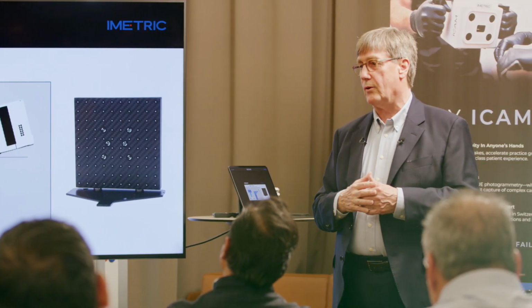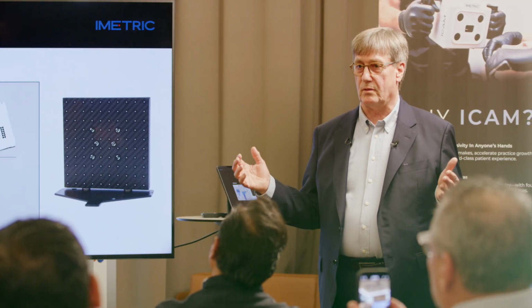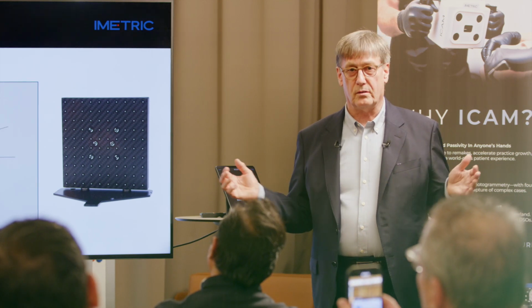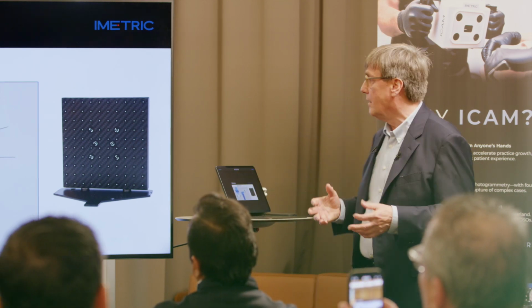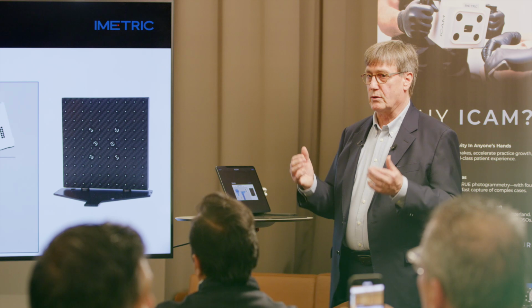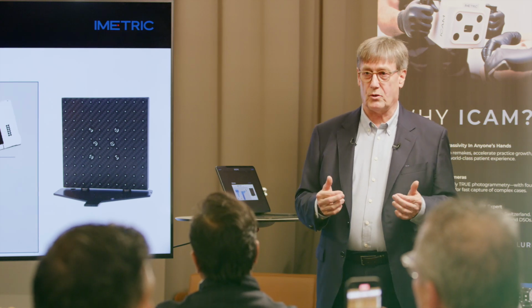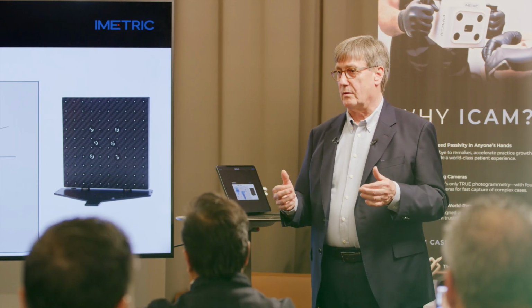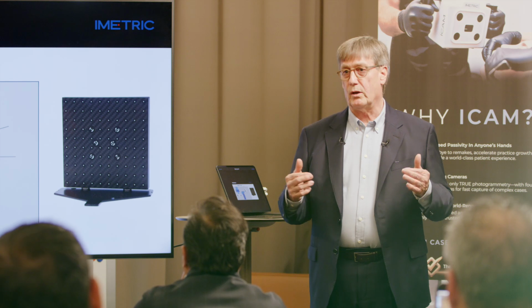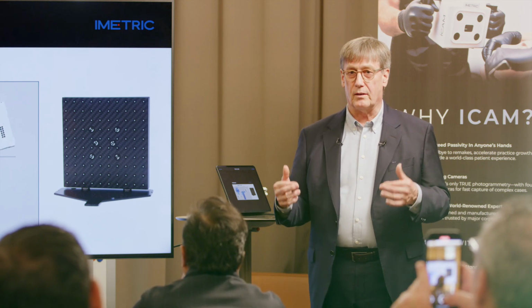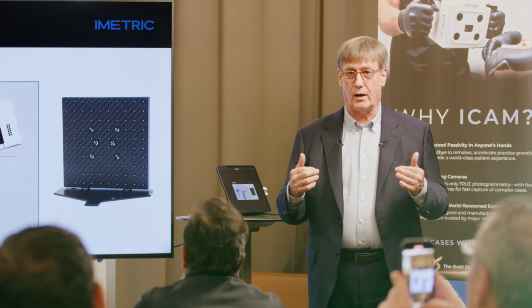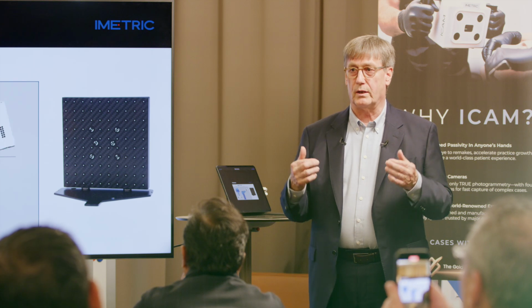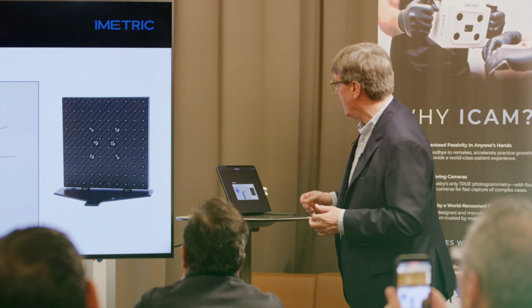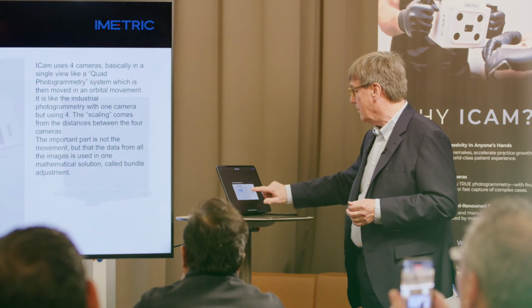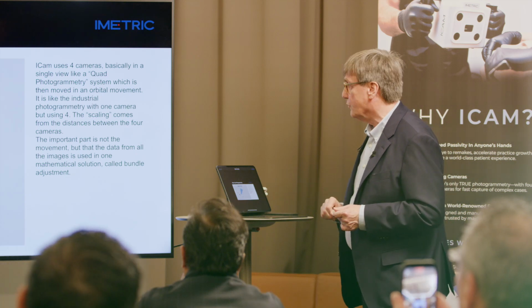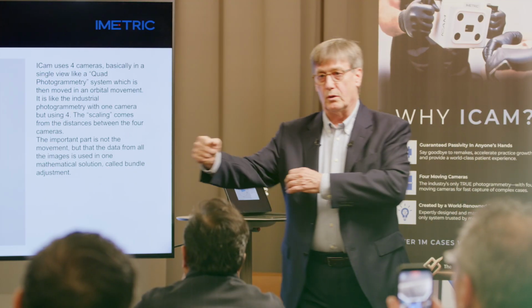You cannot rely on anything once you measure in the mouth. The things are dirty, they are hot, you have no clue what's happening. So we make sure that the system is perfect before we start the measurements. And Switzerland is a democracy, but we are not a democracy. We tell you what we do and how it works. So we force you to calibrate before each measurement. And then we do this movement here. So we do the orbital motion.